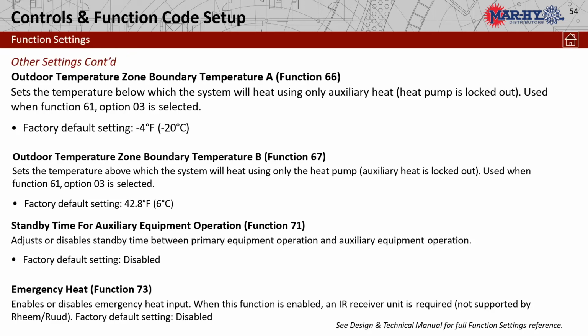Function 73, the emergency heat function. So basically, we are unable to switch the thermostat to an emergency heat setting. There is not one. Mind you, we've already done our emergency heat strips if we have a failure of the outdoor unit, but we do not have the ability to physically turn emergency heat on with no heat pump. It can be done, but it takes an infrared receiver, and there again, it is not supported by RUUD. So we are not going to see this. Remember, your strip heat functions are on the automatic mode, and anytime there is a shutdown of the outdoor unit, an error code, it will automatically go to the strip heat mode.